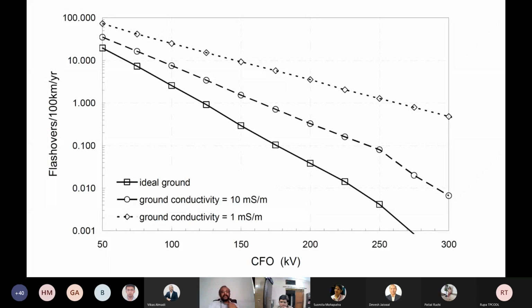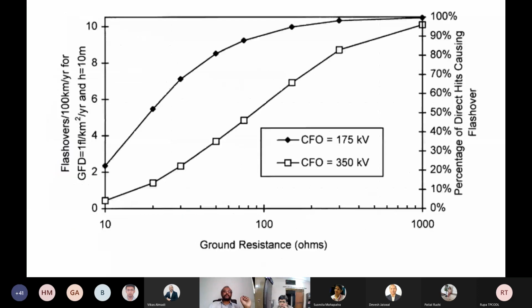So now you can see that if you consider ideal, infinitely conducting ground and do some calculations, then you will find that as the CFO decreases, the lightning flashes to the conductor will increase. And as the ground conductivity decreases, for a given CFO value, the flashes per 100 kilometers per year will increase. This is the same thing I told in the previous slide, and it is the same thing by another diagram, so I will just skip it as it gives more or less the same consideration.